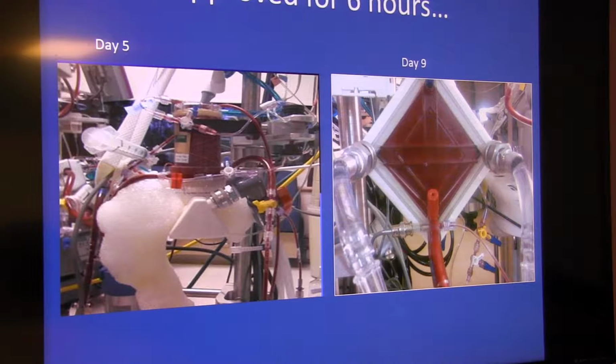Makes sense? So which one do you think has the higher pressure? Pre, right? And you're pushing blood through, you have high resistance within there. So typically when we first put an oxygenator in line, the difference between those two numbers is about 10. So there's a little bit of a gradient, but there's not a big gradient. The protocol to think about when to change that oxygenator is that if you get up to a delta P of 75 across there, or if you have one that's starting to rapidly rise, that would be the indication to change the oxygenator, not necessarily change the entire circuit. 75 or rapidly rising. It's in the manual.